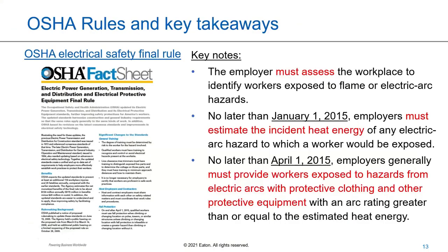So I'm going to jump in just real quick on some of the current codes and standards. I say current, these are the latest and greatest, although a little bit old now, back in 2015 in terms of OSHA. The newer one, 1584, I'll talk about in just a moment. Essentially I'm putting these out here as a reminder: in terms of MV equipment or arc flash zones, typically the rule is, if you've got some piece of equipment, whether it's a transformer secondary or a piece of low voltage equipment, with 40 calories per centimeter squared or greater, it must be de-energized. You're not permitted to work on that per OSHA. And to be quite honest, you wouldn't want to work on that.